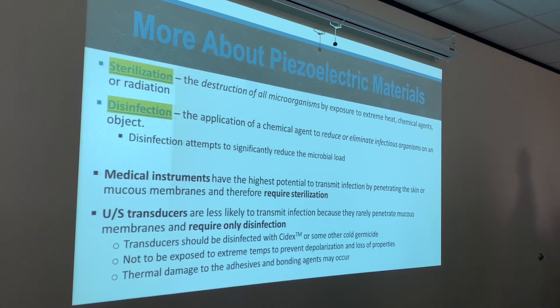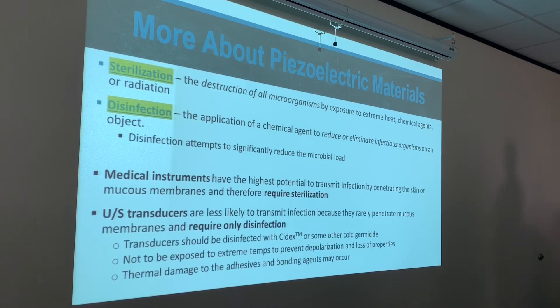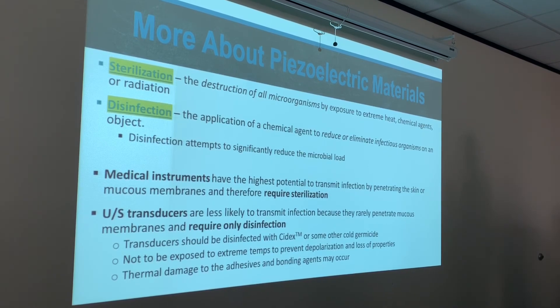Transducers should be disinfected with Cidex or another cold germicide. They should not be exposed to extreme temperatures to prevent depolarization and loss of properties — that's why we don't use the autoclave. Thermal damage to the adhesive and bonding agents may also occur; you may have seen the matching layer peeling up on a transducer — that's heat damage causing the adhesive to fail, which means we lose transducer properties faster.